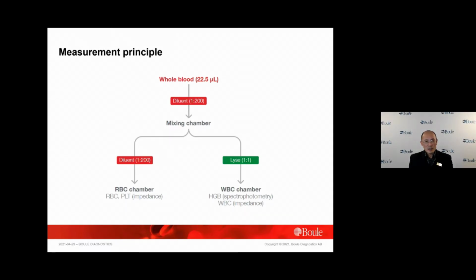For all hematology analyzers using reagent and impedance technology, the task is quite common. That is to measure a precise volume of whole blood and dilute this blood into a highly diluted blood volume in the measuring chamber, and a high dilution ratio gives an advantage for precise measurement. M32 uses two-step dilution. The first step is common for all the parameters. This is a 1 to 200 dilution into the mixing chamber.